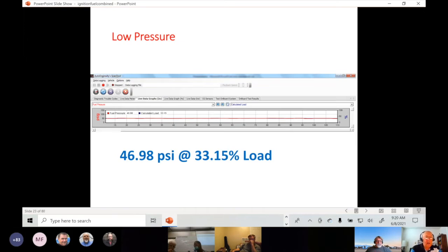Is it important to look at low pressure? Yes. If you have an issue, you need to look at low pressure and high pressure, everything at the same time. You'll notice there's a calculated load here, reprinted down here. You've got about a third load, which is good. If you see 47 psi at 90% load, that pump is on its way out. You'll typically find them between 20 and 40% load.